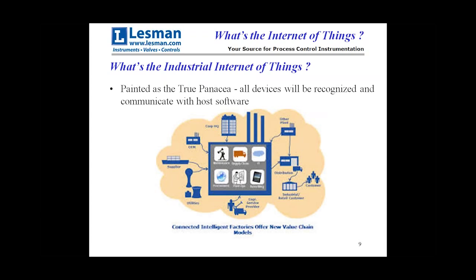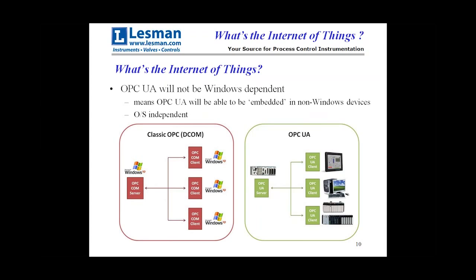OPC UA has been painted as a true panacea — all devices will be recognized and communicate with software. One key way it accomplishes this is by not being Windows-dependent. The classic OPC always required a Windows box for both server and client. OPC UA drops the Windows requirement, making it operating-system independent. The big deal is that OPC can now be embedded directly in devices like PLCs without needing a Windows operating system to run.